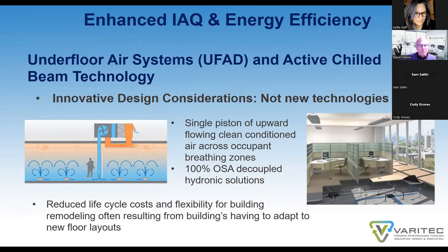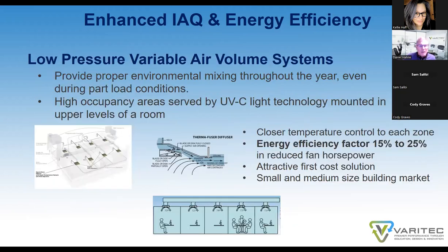Another solution, what about underfloor air systems using active chilled beam technology? That is available today, where we can put an active chilled beam at perimeter zones in an underfloor air system to add another layer of energy efficiency to that type of system. And then we can also do low pressure variable air volume systems, and we can even use variable refrigerant systems for underfloor air solutions as well. So we've been involved in a couple of projects that use this rather effective combination.